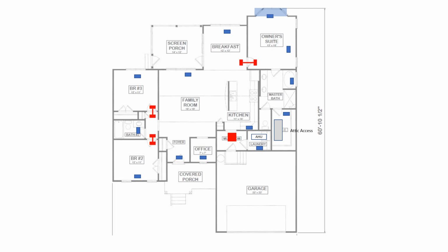Jumper ducts. These can be considered as an unconnected return. These are ceiling grills that are in each room, similar to a small return that connects to a small diameter duct, and the other side of that duct connects to another ceiling grill in the main area. This allows a return path out of the room and back to the main area where the central return is, and you avoid having to run a dedicated return to each room.